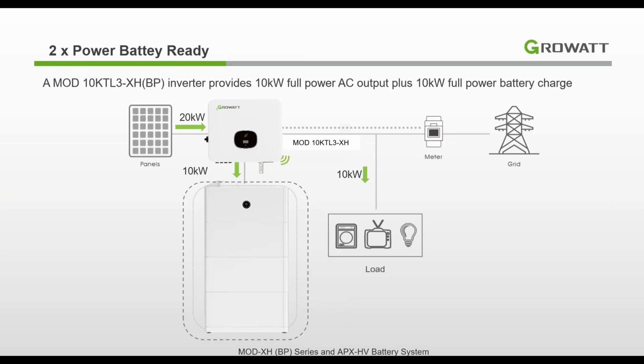Here's an example with the Mod 10 kilowatt: we can receive generation from the panels up to 20 kilowatt, with 10 kilowatt to charge your battery and 10 kilowatt to feed your loads. But remember, because the battery is 0.5C, only half capacity can be charged within 1 hour, meaning a 5 kilowatt hour battery only has 2.5 kilowatt charge and discharge power. So if you want to reach the maximum power rate of this inverter, which is 10 kilowatt, you will need four batteries, 20 kilowatt hour in total at least, to achieve 10 kilowatt charge and discharge power.